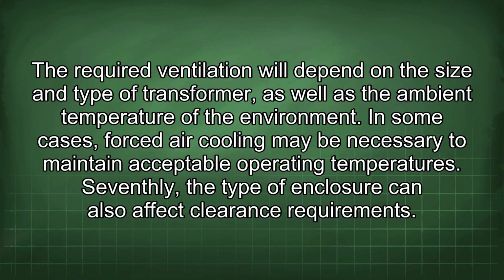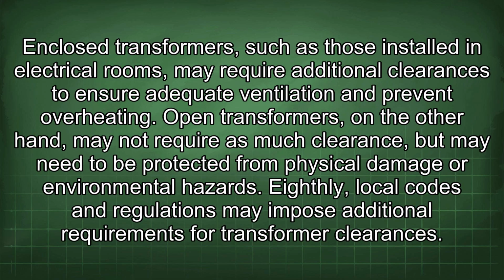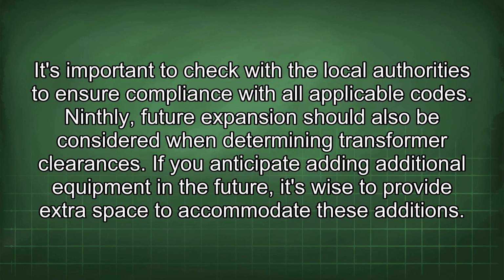Seventhly, the type of enclosure can also affect clearance requirements. Enclosed transformers, such as those installed in electrical rooms, may require additional clearances to ensure adequate ventilation and prevent overheating. Open transformers, on the other hand, may not require as much clearance, but may need to be protected from physical damage or environmental hazards. Eighthly, local codes and regulations may impose additional requirements for transformer clearances. It's important to check with the local authorities to ensure compliance with all applicable codes.